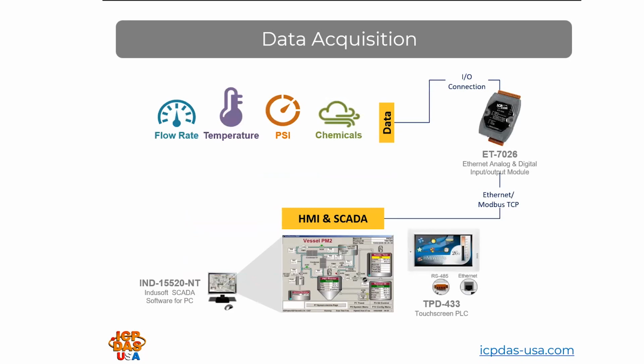Data acquisition is the gathering of physical information like flow rate, temperature, pressure, or pH data, and the conversion of those signals into information that computers and controllers can understand. The ET7026 Modbus TCP-based analog and digital I/O module gathers the information through sensors connected to the terminal block connector. The data is passed over Modbus TCP through Ethernet cabling to a computer running Windows operating system and a ladder logic and C language touchscreen controller.